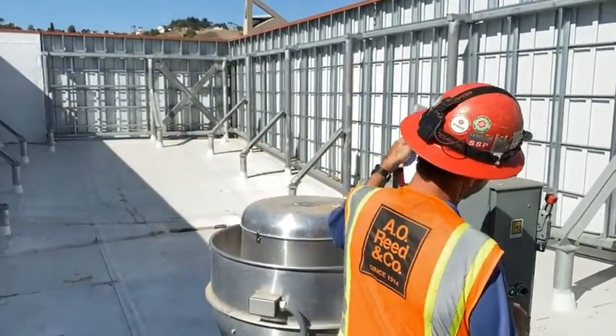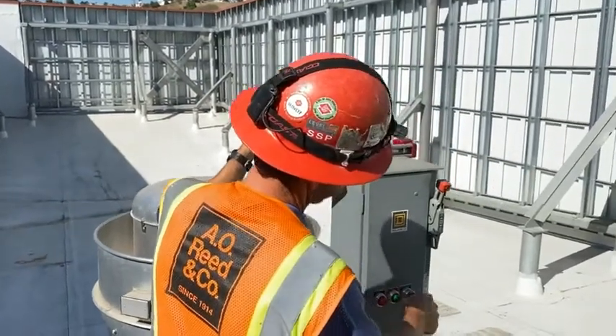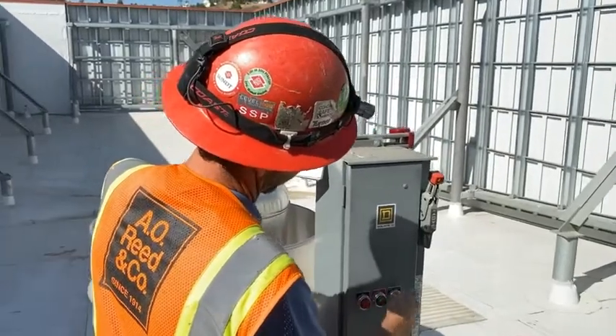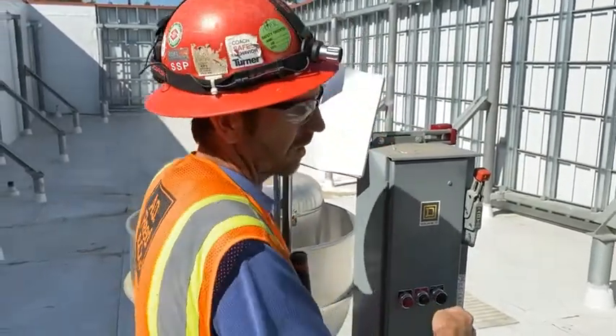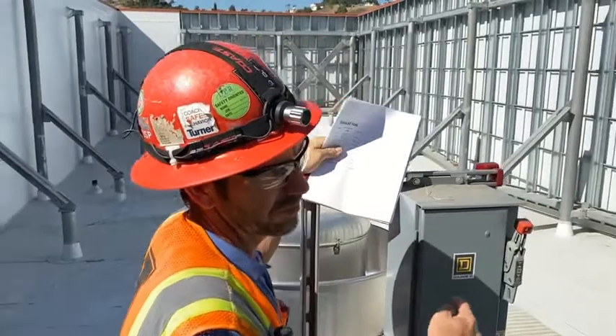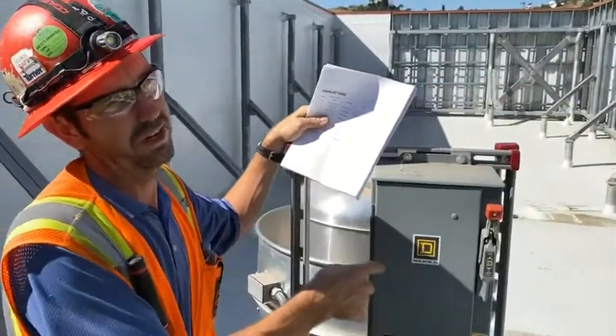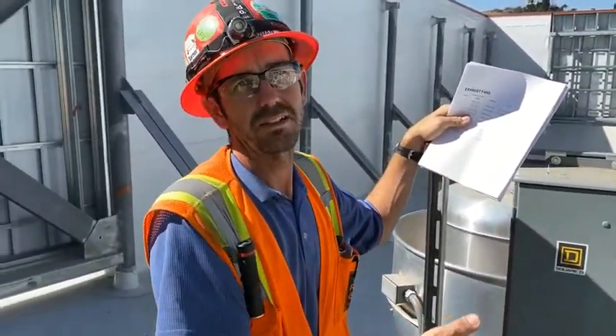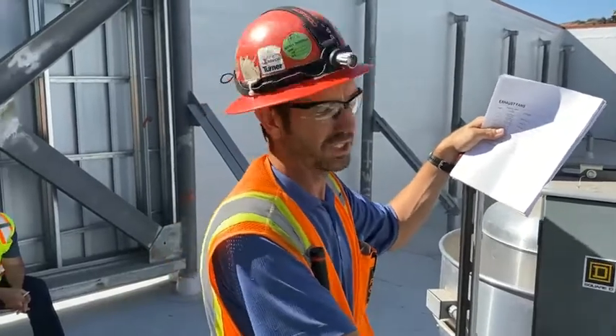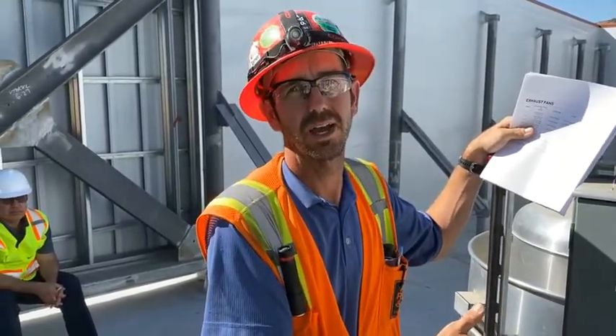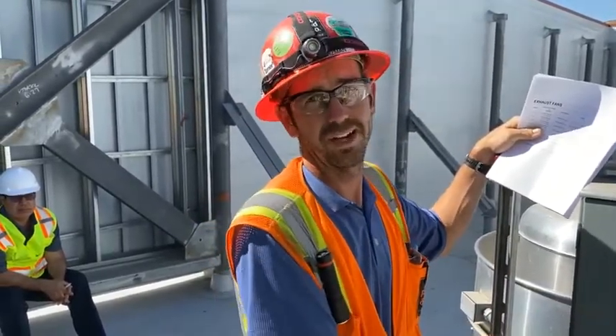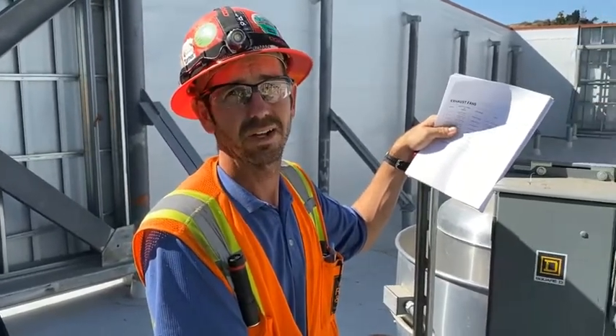Since it's an Ansul system, the auto switch doesn't really do anything, or off. The starter's wired from the 24 volt transformer straight to the contactor. Because if the Ansul system's running this, it doesn't matter what the switch is, we need it to turn on no matter what, okay? But the unit will turn on in hand up here, as of now, okay?